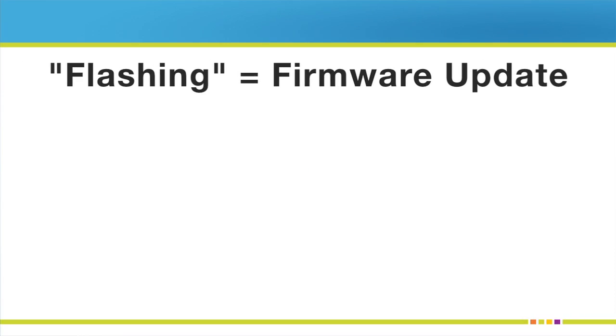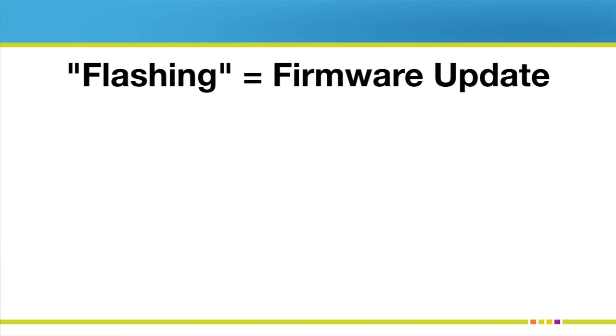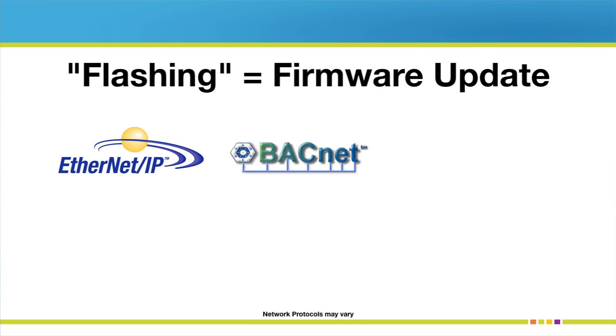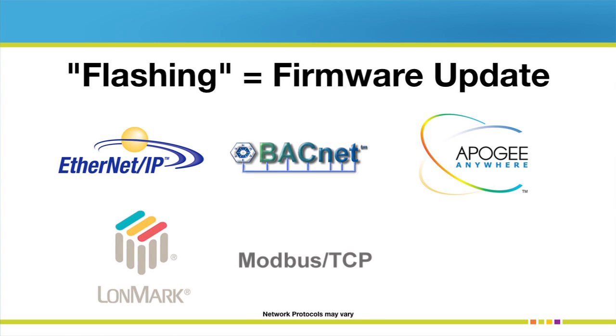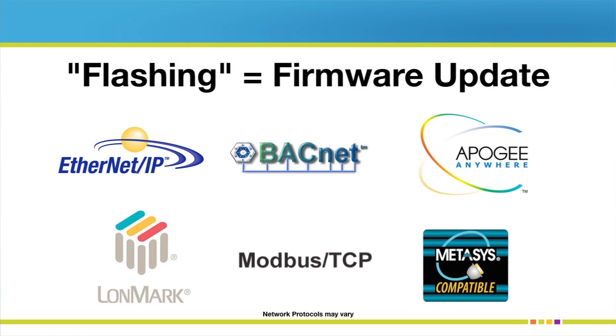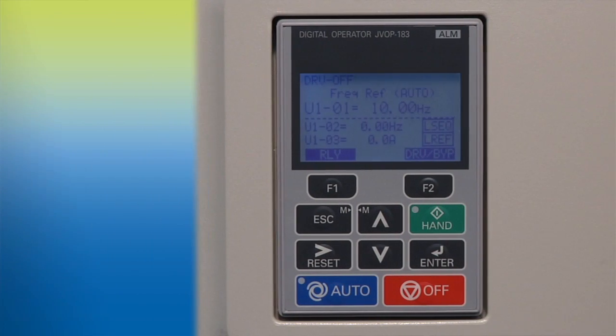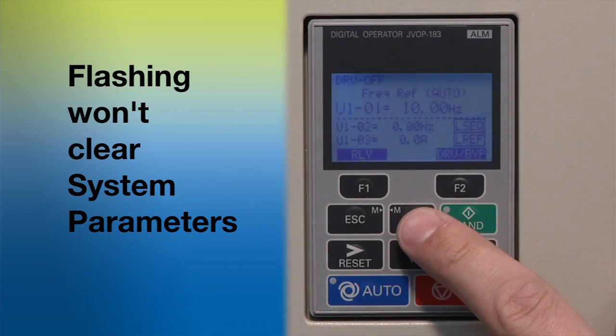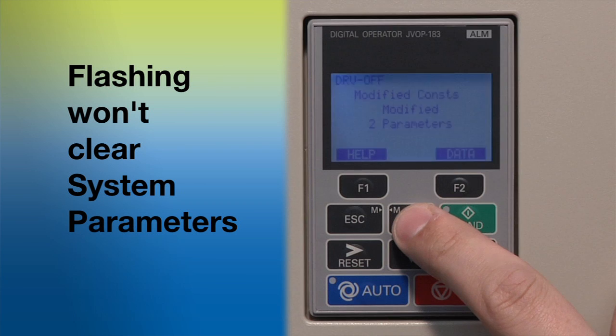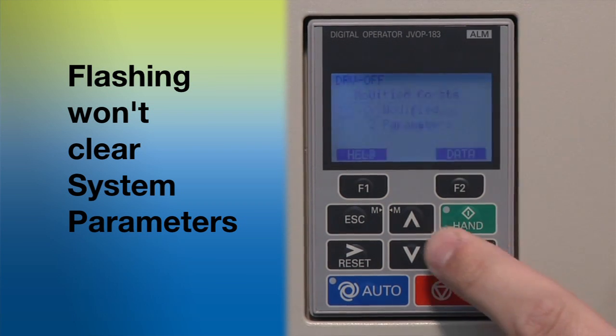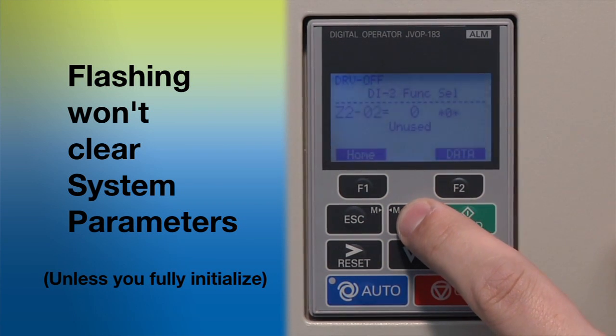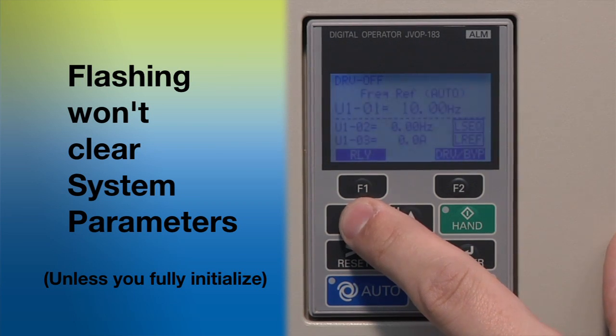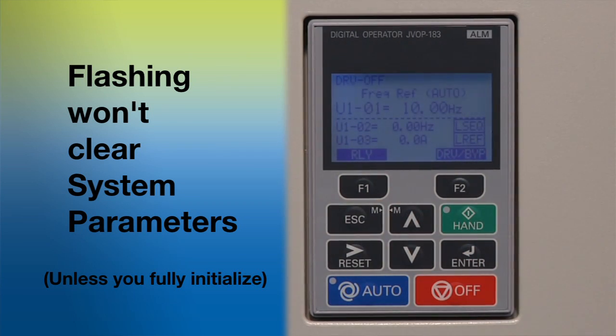Now, when we use the term flashing, we mean that we're updating the data file that stays resident in the unit's firmware. Flashing keeps your software up to date with the latest fixes. In some cases, it can also add the ability to connect with the latest versions of common networking protocols. It is important to note that flashing won't clear out the system's current programming. You won't need to set up the drive's parameters or operating functions all over again, unless you go beyond flashing to fully initializing the drive. That isn't likely, however, because you don't commonly need to initialize when you flash a drive.